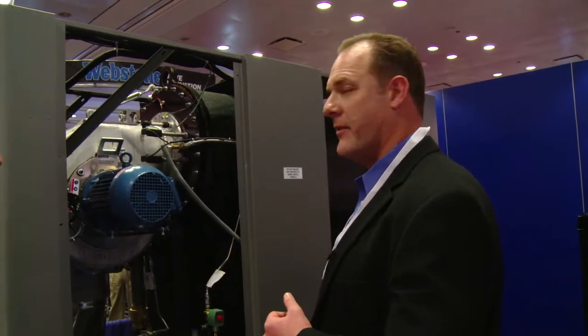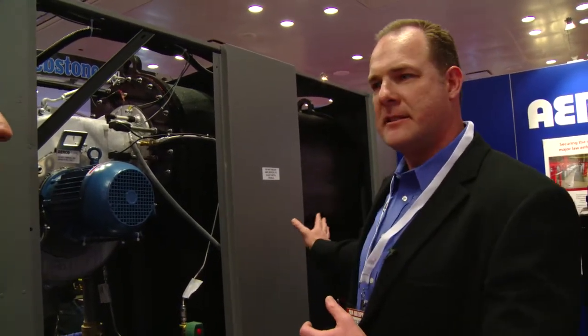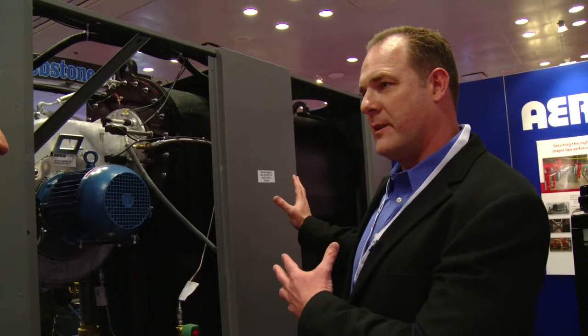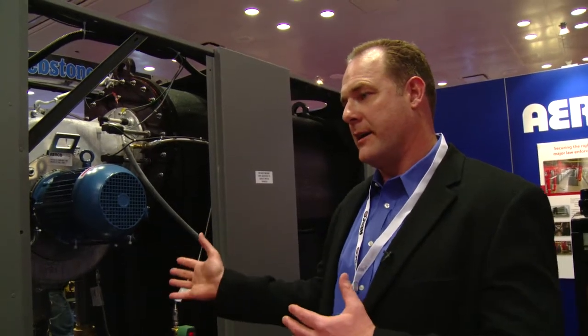But AERCO also offers accessories for this product, and one thing that we haven't touched on is the venting. In today's world, as you probably know, Dan, some of the venting installations can be just as costly as the boiler products. Sure. Because of the efficiencies of this product, it's actually listed to be able to, on the 6 million, to apply polypropylene venting because of the low temperatures of the exhaust gases. And on the 3 million and below in this product, we can actually apply it with PVC venting.